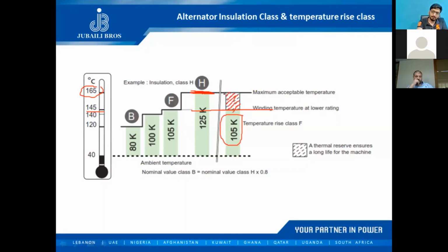Okay, so I have a 100 kVA alternator, but I'm only using it as a 90 kVA alternator. I'm not pushing it to its limits. So when we talk about temperature rise class, it's not that you will purchase an alternator of temperature rise class F or temperature rise class H or whatnot. It's how we use the alternator.